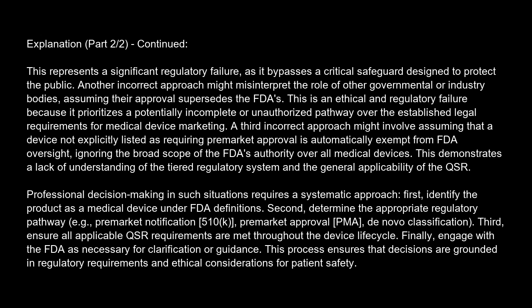Professional decision-making in such situations requires a systematic approach. First, identify the product as a medical device under FDA definitions. Second, determine the appropriate regulatory pathway, e.g., Pre-Market Notification 510(k), Pre-Market Approval PMA, de novo classification. Third, ensure all applicable QSR requirements are met throughout the device lifecycle.